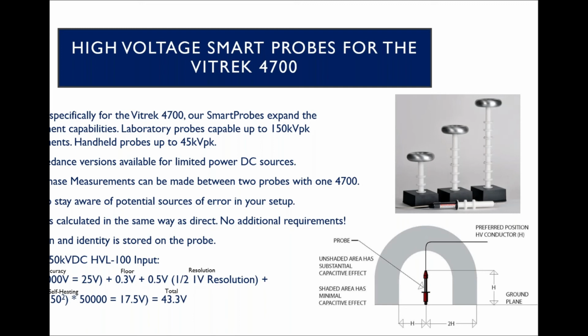on your source. In addition, you can also make phase-to-phase measurements with 2 probes with one 4700. Simply connect your 2 probes and apply one phase to one probe and the other phase to the other probe, or differential measurements on DC as well can be made that way. So you always want to be sure to stay aware of those potential sources of error in your setup. With the larger equipment and the additional equipment, your spacing is going to be a lot more pertinent to your accuracies. So there's a nice little chart down in the bottom right there of the screen that really helps show what area has an effect around a probe, and really how you should connect it to really ensure your highest accuracy capability. If any of those are influenced within that unshaded area around the probe, you could be having very large effects to your accuracy there.